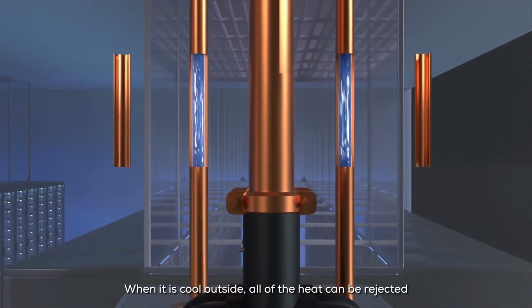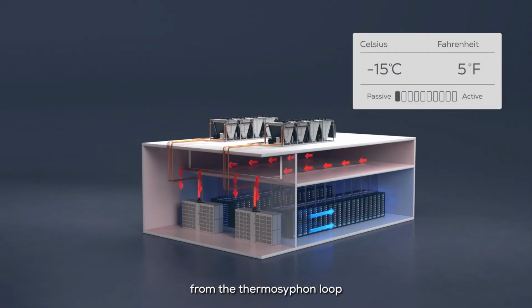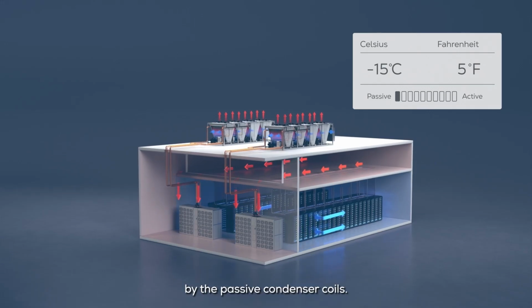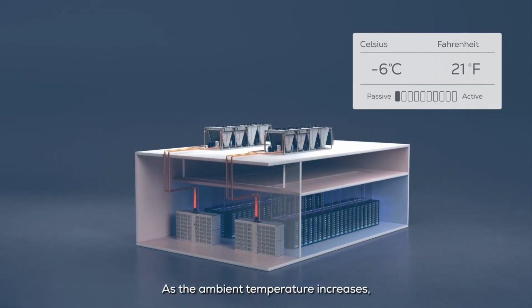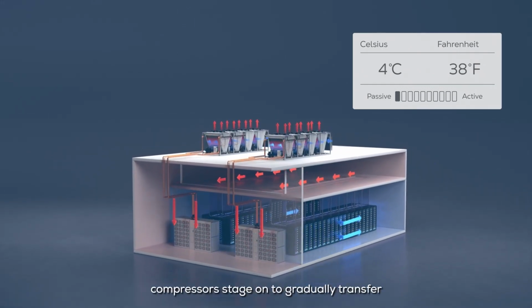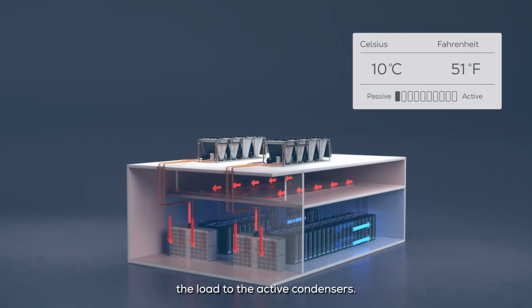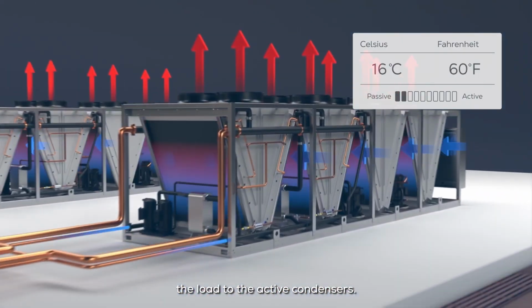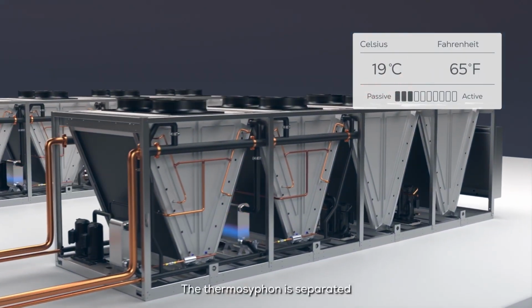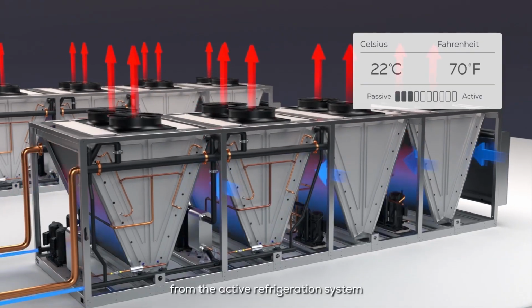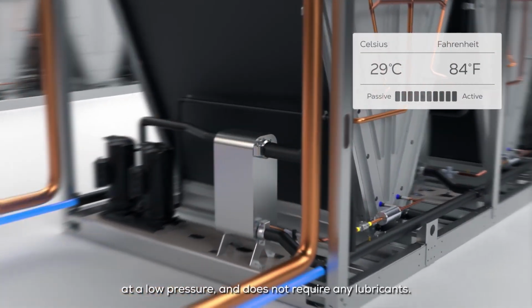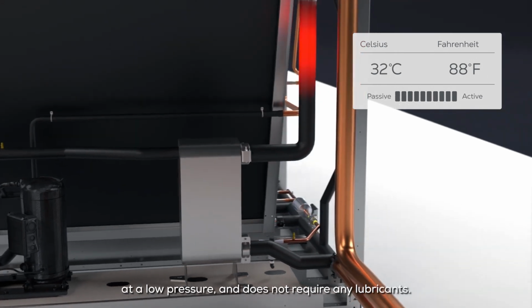When it is cool outside, all the heat can be rejected from the thermosiphon loop by the passive condenser coils. As the ambient temperature increases, compressors stage on to gradually transfer the load to the active condensers. The thermosiphon is separated from the active refrigeration system by a heat exchanger and always operates passively at a low pressure and does not require any lubricants.